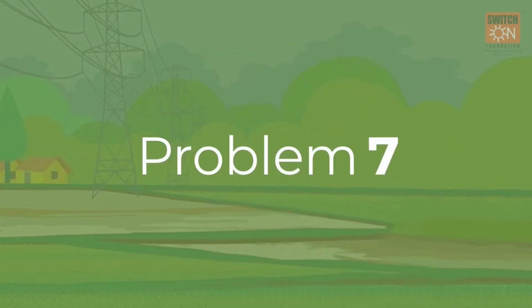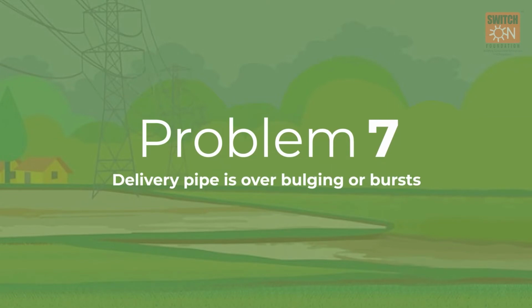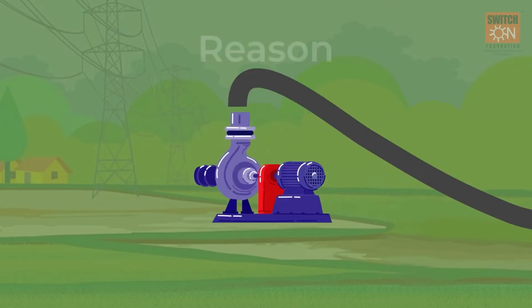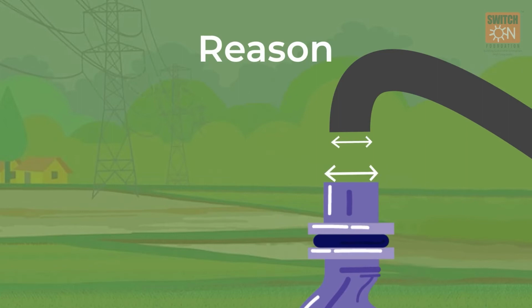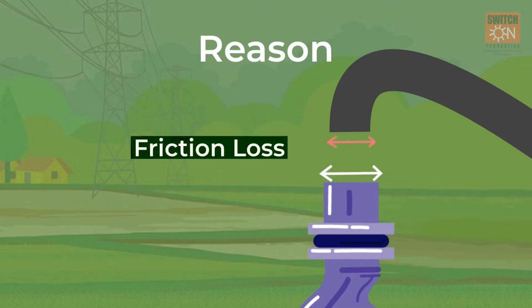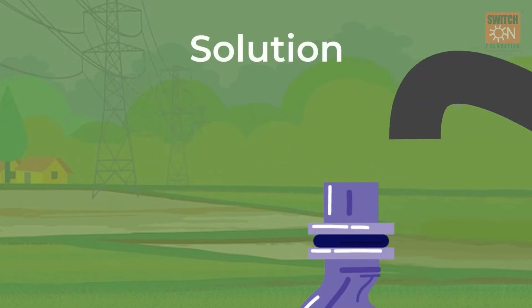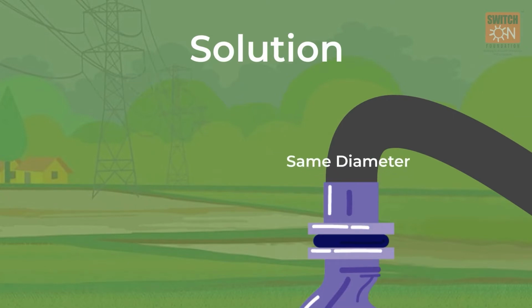Problem 7. Delivery pipe is over bulging or bursts. Reason: the delivery pipe diameter is smaller than the pump output pipe diameter or nozzle diameter, causing friction loss. Solution: use a delivery pipe of the same diameter as the output pipe or nozzle.